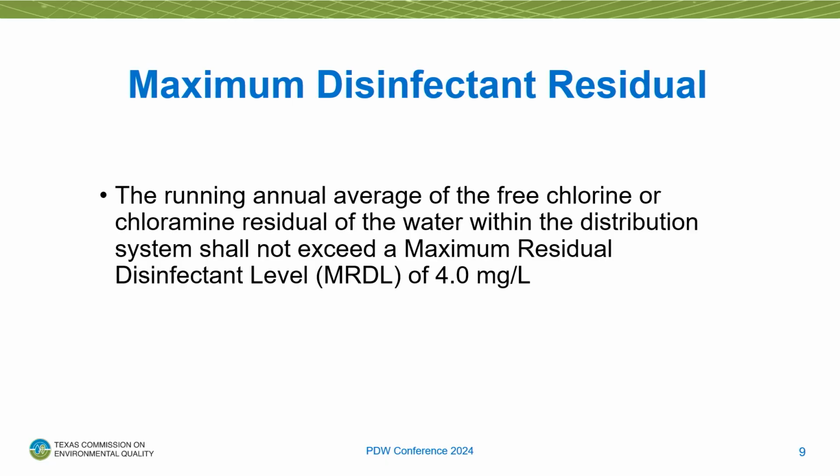Next, on the other side, we've got the maximum disinfectant residual. That's going to be for both free chlorine and total chlorine, and it is 4.0 milligrams per liter. Exceeding the maximum is costly and has negative health effects. Some of the side effects are stomach and throat irritation, nausea, vomiting, not good stuff. You don't want that for your customers.